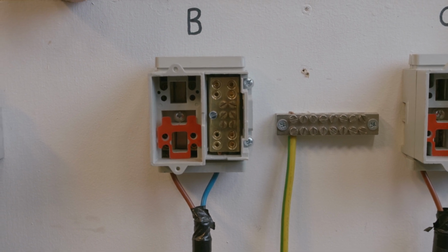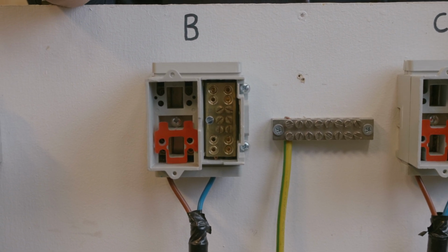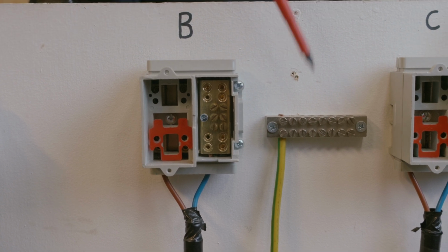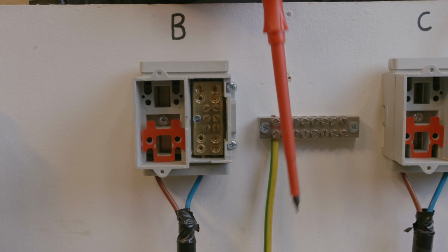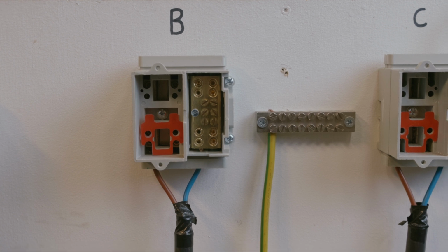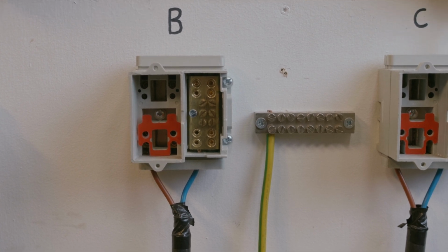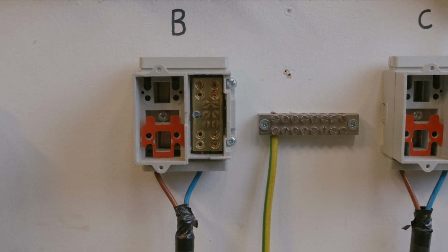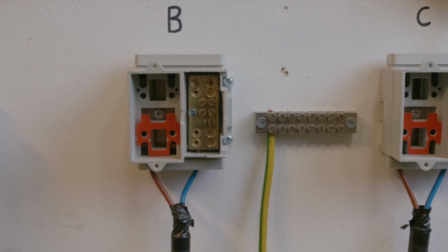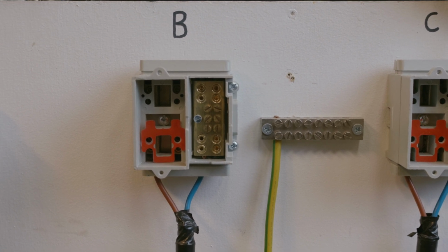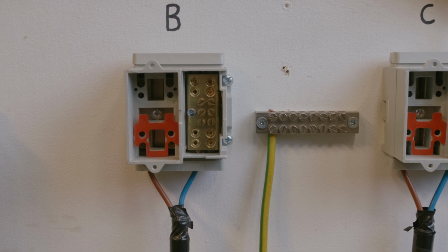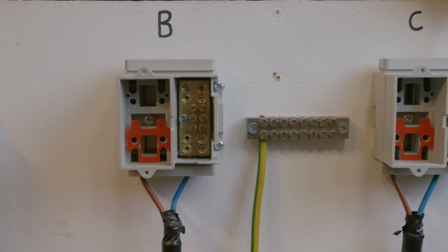And this is probably quite an easy one to find. The only problem you may come across is if that earth electrode is at a different point to where the supply coming in is, then it might take a bit of looking before you find it. But hopefully that should be identified and labelled to show that it's the earth electrode, and it should be in a suitable pit in the ground as well.